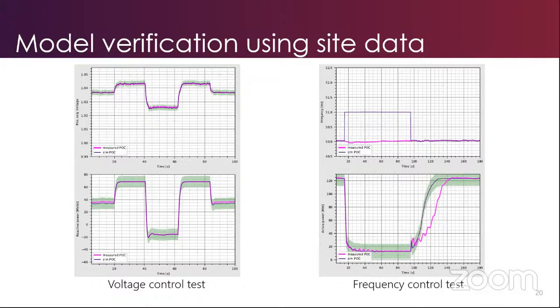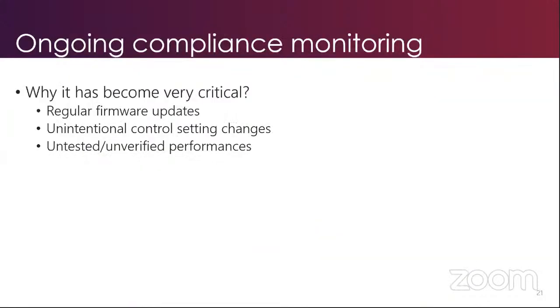There are some imperfections. We make an engineering judgment; say in the frequency control test, we might say, okay, this is not acceptable, you have to improve the model to match the plant. Sometimes, if it's reasonable, we might say, okay, this is fine, and it might not have an impact on the studies we do. So model verification at the completion of testing is an important part, as we're going to use those models in any upcoming studies. Lastly, ongoing compliance monitoring is critical because we cannot test everything at the site.